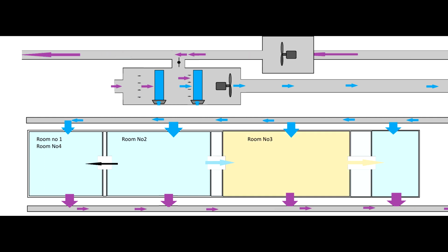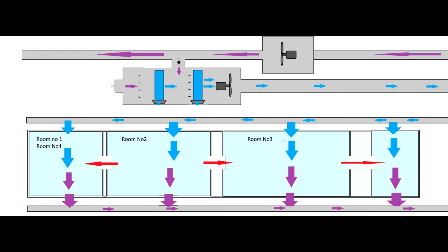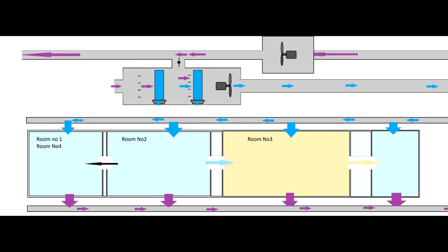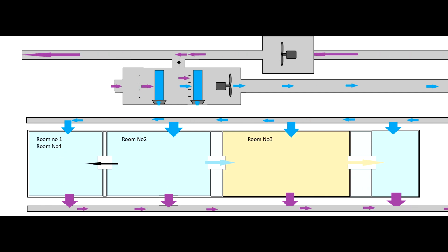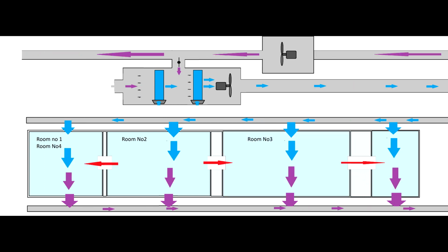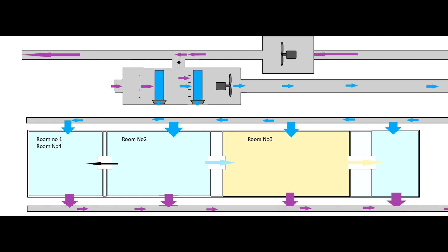So this is the system I'm talking about. You have an air handling unit which provides air to a group of rooms where the production takes place. You don't want to restrict the air here. That's why you have to make sure that the heat exchanger never ices up. But what am I going to do? Because the system is already using minus 15 degrees glycol. I have to build a buffer. I have to reorganize the pipes. I have actually to change the design and the control philosophy.